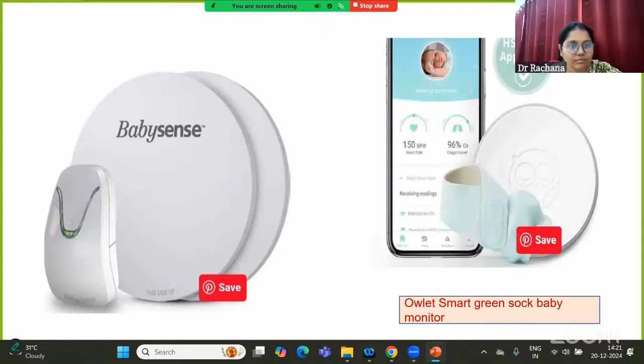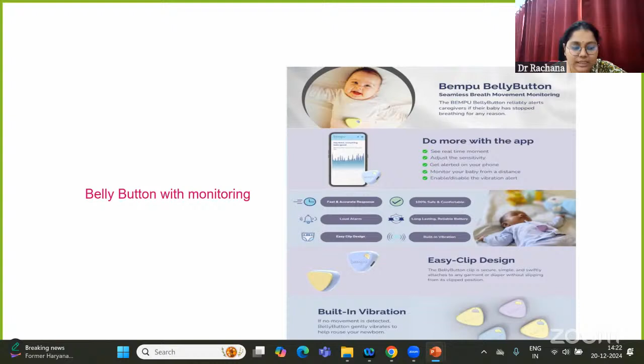This button can be fixed to the diaper, but it has to be in touch with the baby's body surface area. And if at any point there is apnea, up to 20 seconds, you can set the time, say 20 seconds. Then even after the 20 seconds, if there is no body movement, it gives the vibration, and this can be connected through Bluetooth to the phone, and even gives the alarm to the phone also. Even after vibration, if the baby doesn't breathe, again it vibrates and gives the alarm to the phone. It's quite helpful in the NICU as well as in home monitoring.